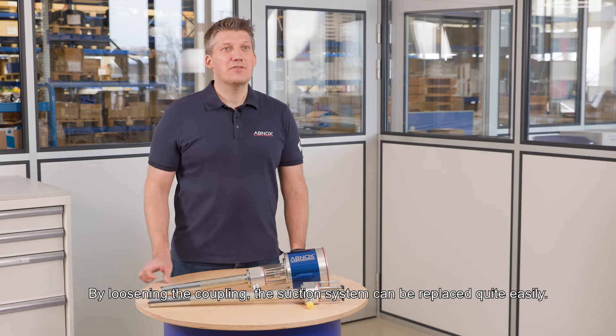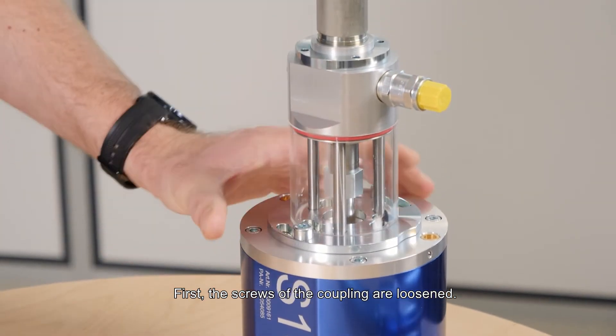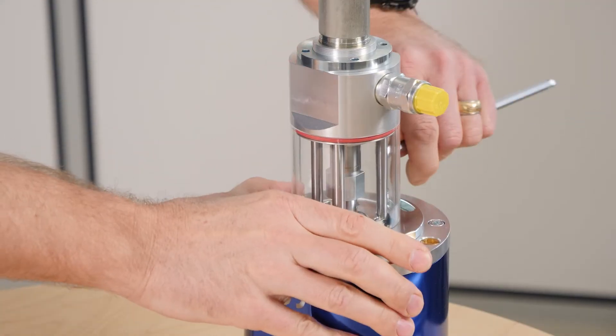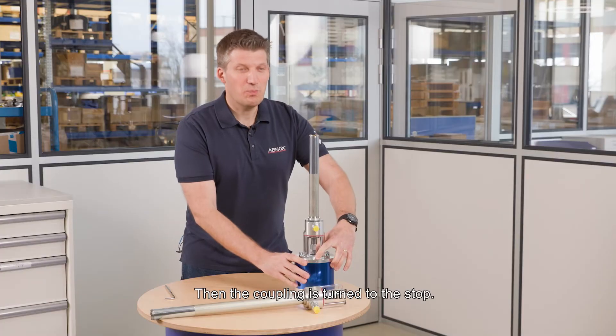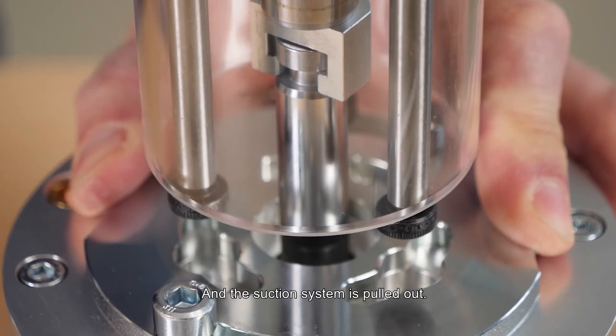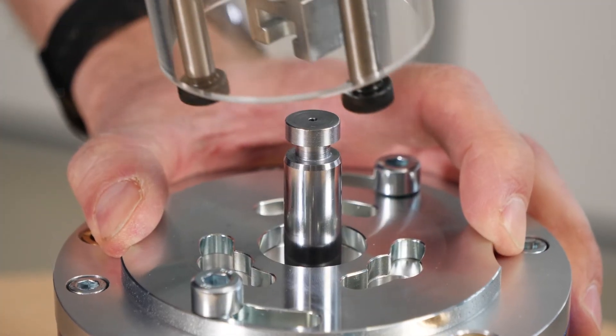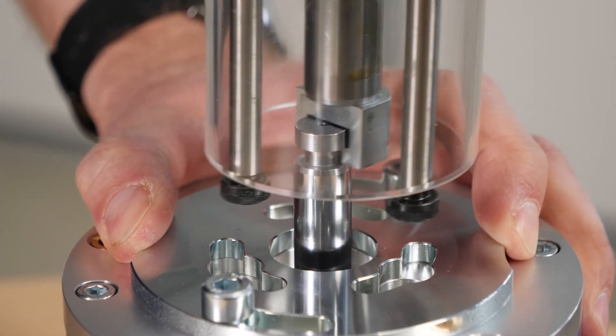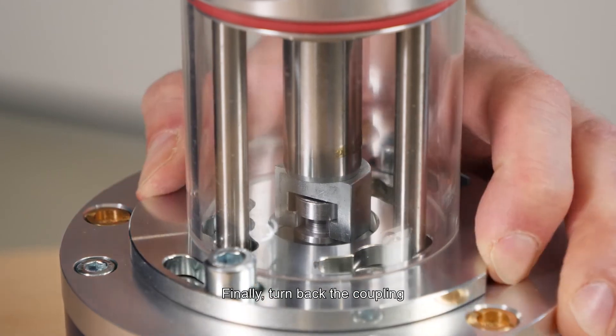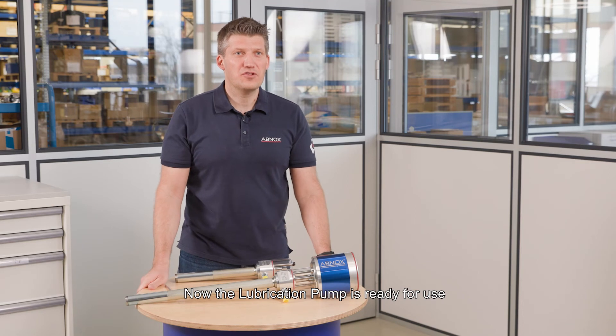By loosening the coupling, the suction system can be replaced quite easily. First, the screws of the coupling are loosened, then the coupling is turned to the stop and the suction system is pulled out. Then take the new suction system and insert it. Finally, turn back the coupling and tighten the screws. Now the lubrication pump is ready for use.